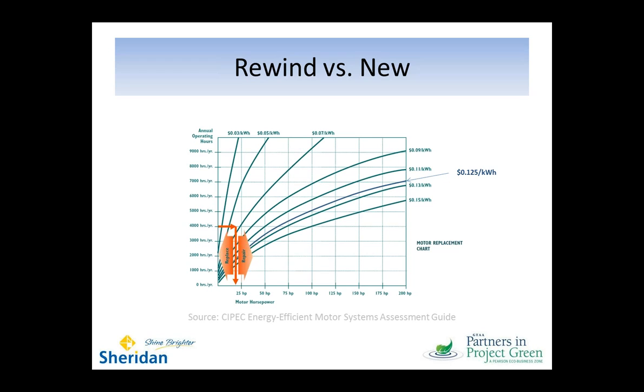And if I'm going to the left, then I might want to send it to rewind. And there are some rules of thumb here we can apply. Again, the one is that if you've got a motor with a defective stator core, don't rewind it. And if you can't restore that thing, just replace it with a new premium efficiency motor.